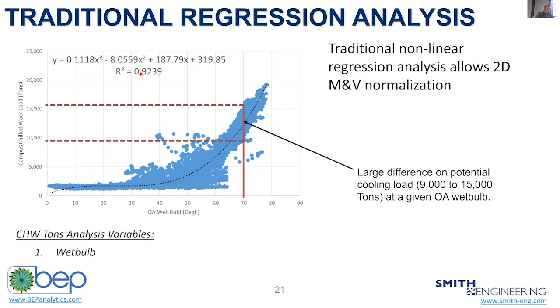Then I get an R squared value of 0.92, or even if I delete these data sets out here, I could get myself up to 0.97, and I feel really, really great about myself because my R squared is 0.97. But then I look at it and I'm saying, hey, wait a second here. This is misleading. Yes, I'm close to this line, but let's look at it in reality. Okay, 70-degree wet bulb. The equation is going to tell me that that is, what is that, 12,500 tons. But wait a second, the actual data could be 16,000 tons or 9,000 tons. I mean, that's such a big deviation. This is completely worthless from a prediction standpoint. So we have to get better.